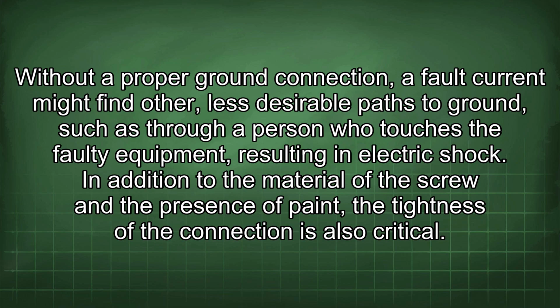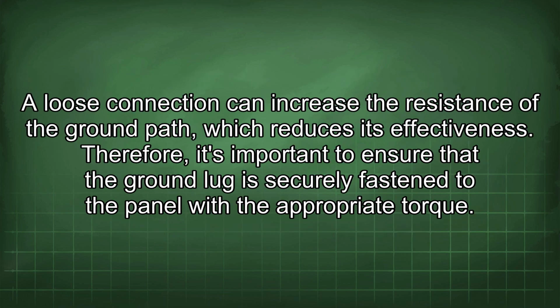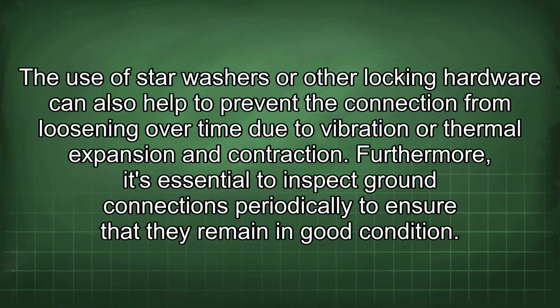In addition to the material of the screw and the presence of paint, the tightness of the connection is also critical. A loose connection can increase the resistance of the ground path, which reduces its effectiveness. Therefore, it's important to ensure that the ground lug is securely fastened to the panel with the appropriate torque. The use of star washers or other locking hardware can also help to prevent the connection from loosening over time due to vibration or thermal expansion and contraction.